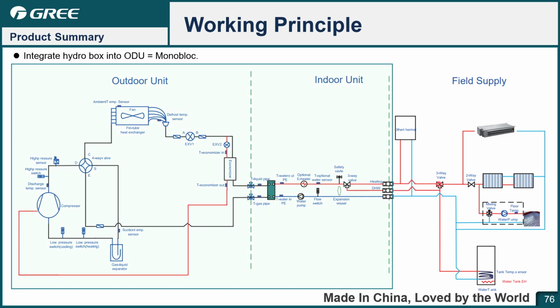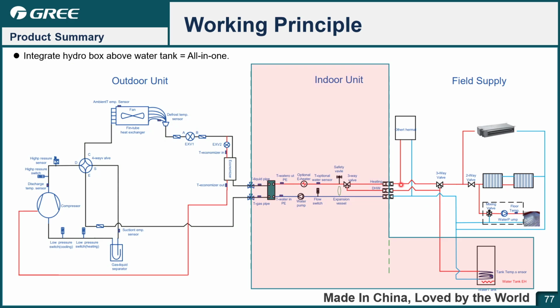However, if the outdoor unit and the indoor unit hydro box are together, so actually you integrate the hydro box into the outdoor unit, that's the monoblock, and you just need to connect the water pipe system. Next, if the indoor unit and the water tank are integrated together, you just connect the refrigerant pipe and the FCU, floor heating, radiator water pipe. For this part, these two water pipes connect directly to here. So that's the difference between the split, all-in-one and monoblock VERSATI 3.